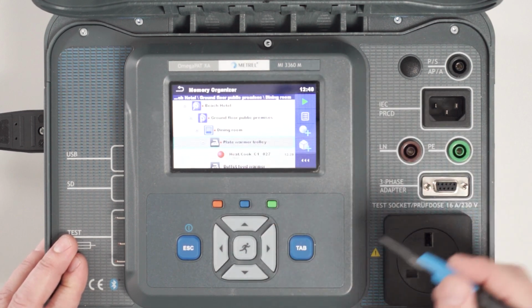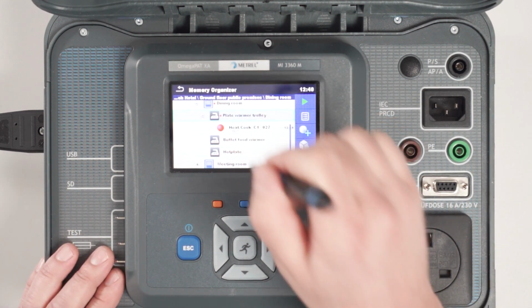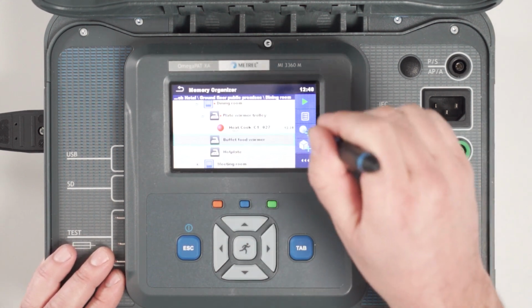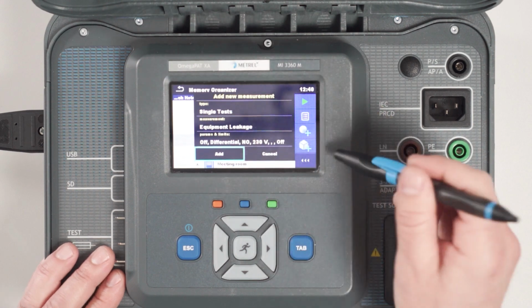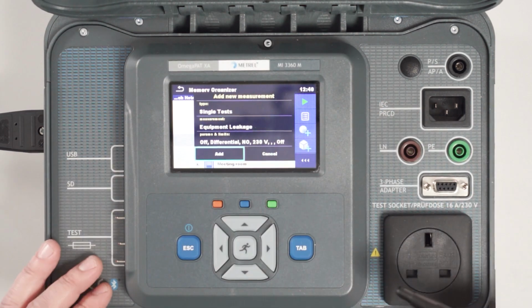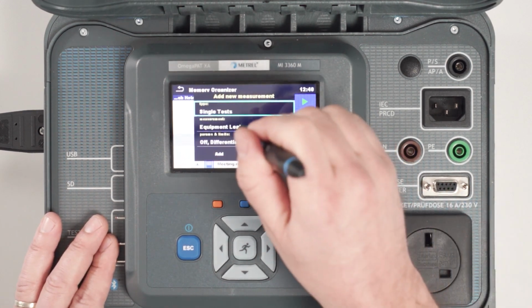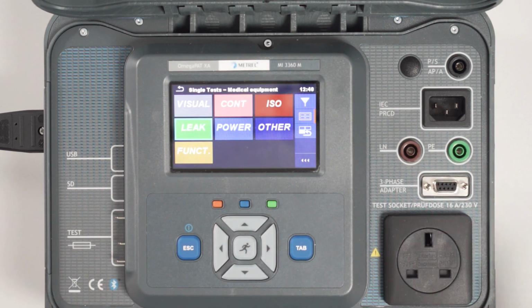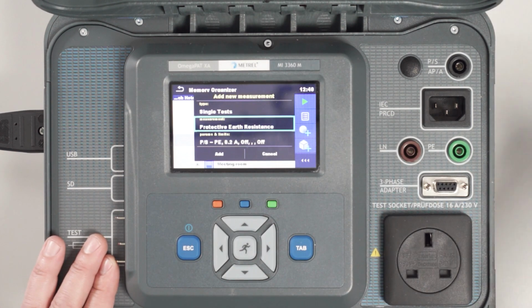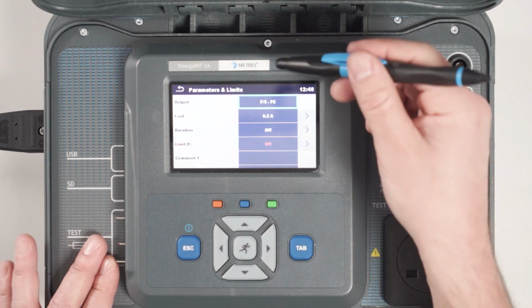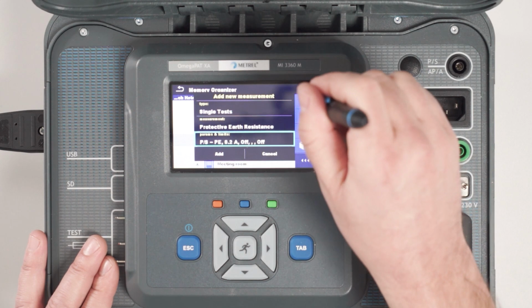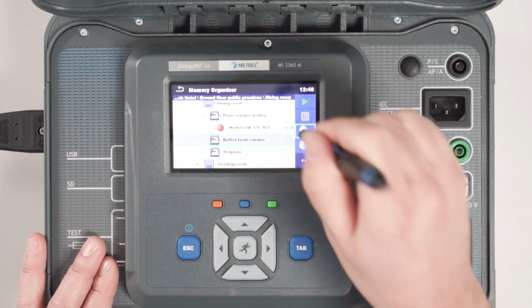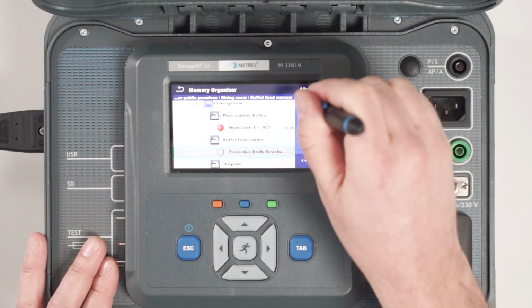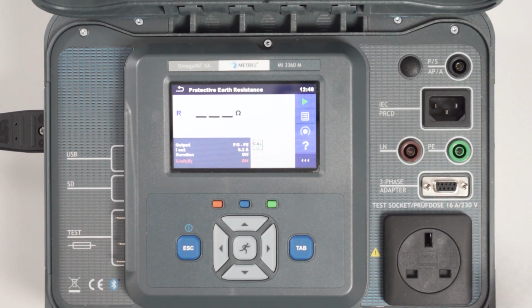Same can be done via single measurements. So for example, if we go to the next structure element, we click on add measurements, and this shortcut will lead us back into the single test menu. So we go either single test or auto sequences, and we simply select one of the available single tests inside this menu. For example, earth continuity. We set our limits and simply press one step back like this, add, and simply press start.